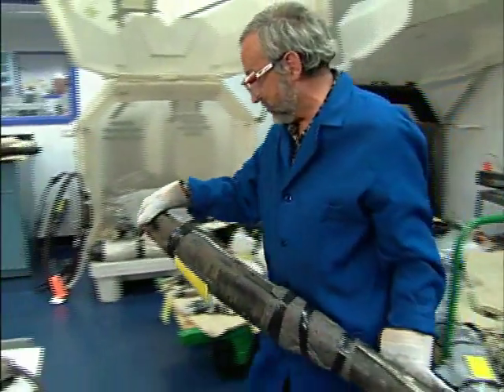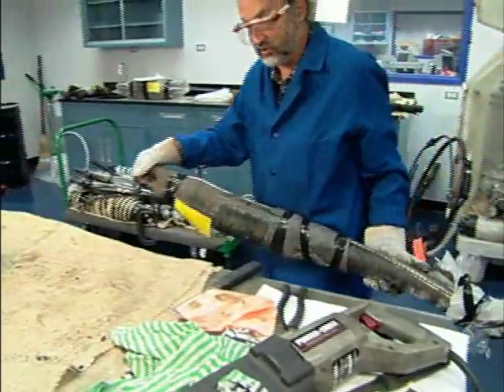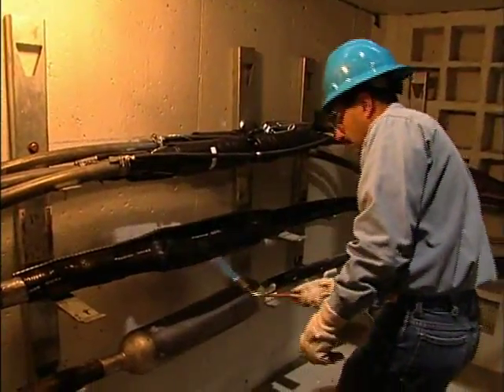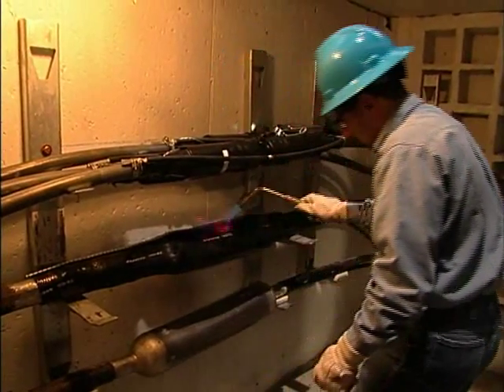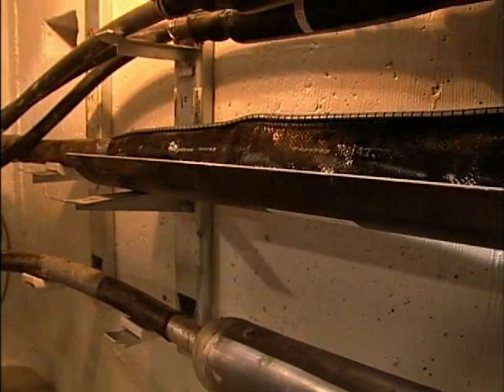At Con Ed and Public Service, if a joint fails within the first 5 years of installation, the technicians who installed it may be invited to attend the autopsy. But the more you know about how joints are designed and what each component does, the easier it will be for you to make a joint that achieves the goal of lasting longer than the cables that you have joined.